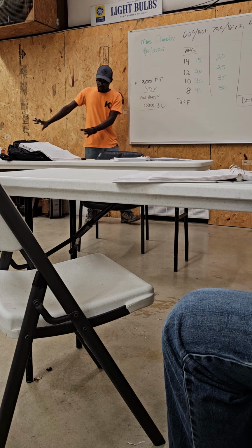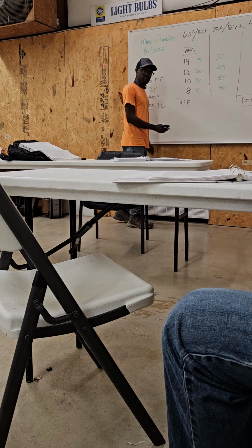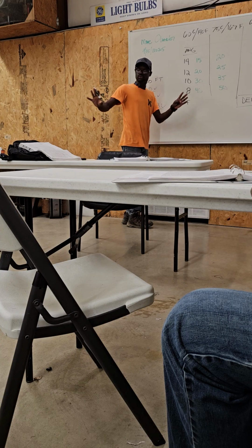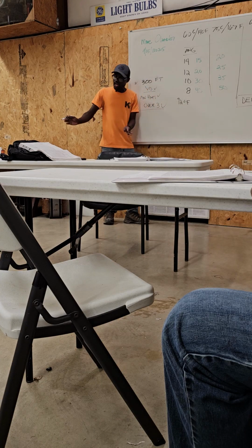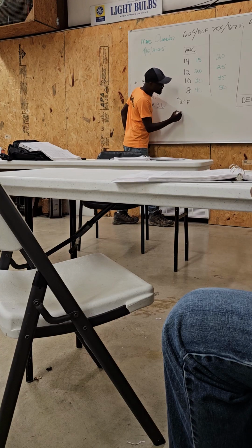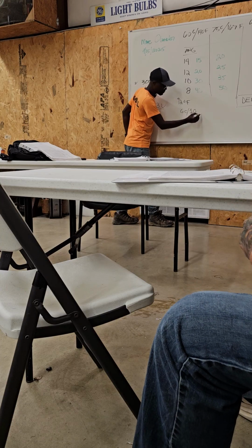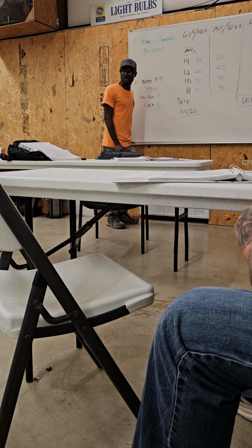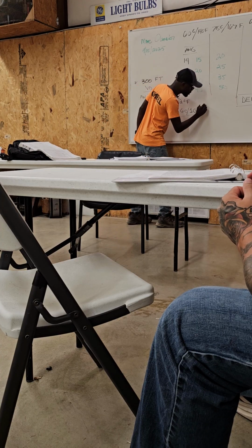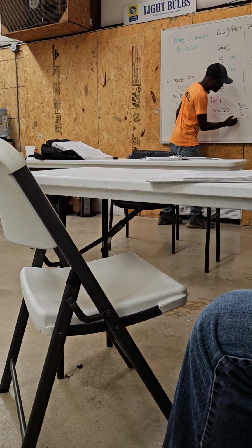Okay? So we are running for light. Let's say, since I'm going distance, I have 6, they were 2-way. I didn't have a neutral, so everything was 2-way. All I have is the ground and 2 conductors. So let's say I have 6 conductors in that part with a ground. How many wires do I have? 7. But how many are actually carrying current? 6. So now I have 92 degrees and I have 6 conductors. This is how that works.